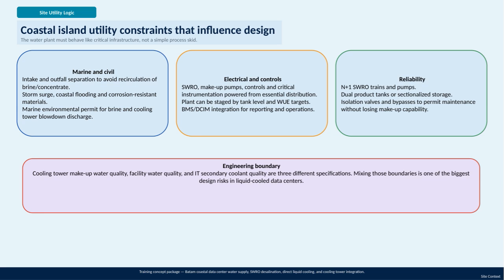We also designed the plant to be staged based on tank levels and water use efficiency targets, making it adaptable and efficient. Integration with the building management system and data center infrastructure management tools enables detailed reporting and streamlined operations. Reliability is a major focus, so we implement an N+1 redundancy for both the SWRO trains and pumps. We also design dual product tanks or sectionalized storage to provide flexibility and continuous supply. Isolation valves and bypasses are incorporated, allowing maintenance activities without interrupting the makeup water supply.